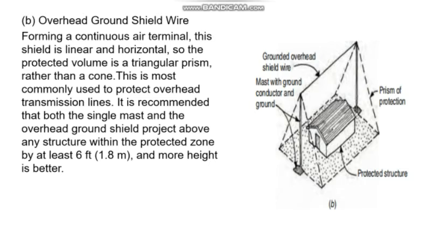Next example is the overhead ground shield wire. Forming a continuous air terminal, this shield is linear and horizontal, so the protective volume is a triangular prism rather than a cone. This is most commonly used to protect overhead transmission lines. It is recommended that both the single mast and the overhead ground shield project above any structure within the protected zone by at least 6 feet, and more height is better.